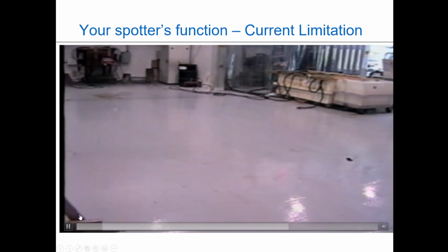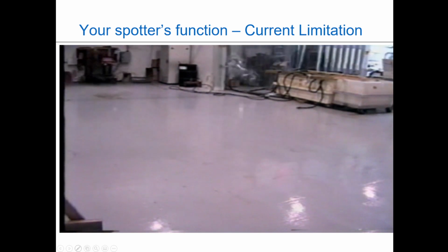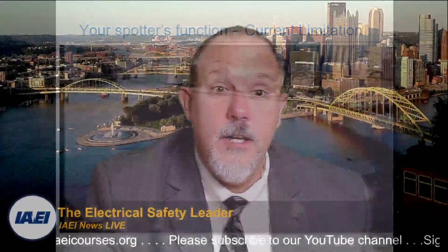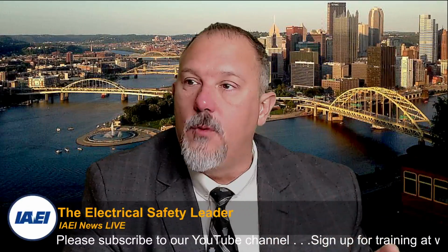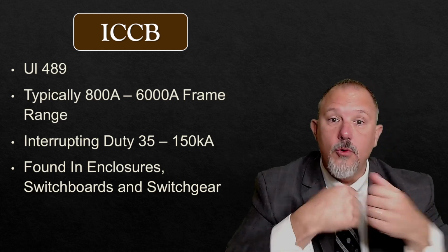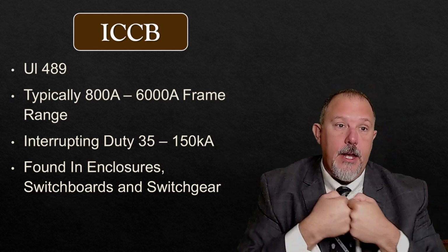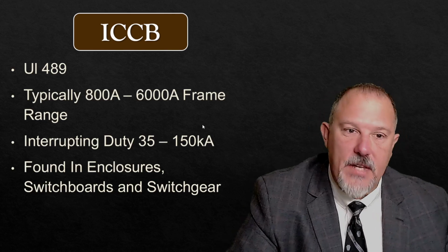All right, I'm going to show that to you one more time. That is a significant amount of magnetic forces that an insulated case circuit breaker or power breaker has to withstand to hold those contacts closed and not achieve an unintended rapid disassembly in the field.